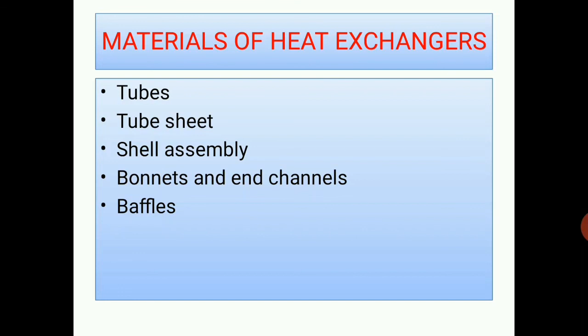Next, the shell assembly. The shell is constructed either from pipe or rolled plate metal. For economic reasons, steel is the most commonly used material, and when the application involves extreme temperature and corrosion resistance, other metals or alloys are specified. Next one is the bonnets and end channels. Bonnets and end channels regulate the flow of fluid in the tube side circuit. They are typically fabricated or cast. Next one, the baffles. The baffle functions in two ways. During assembly, they function as tube guides, and in operation, they prevent vibration from flow induced eddies.